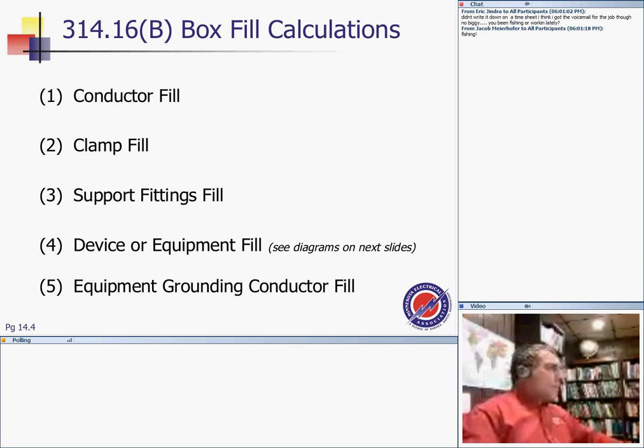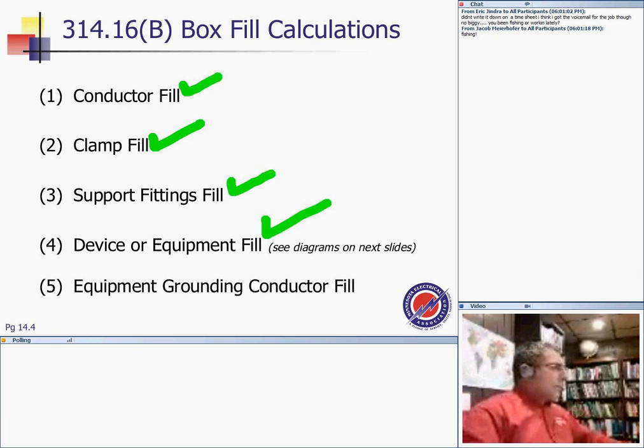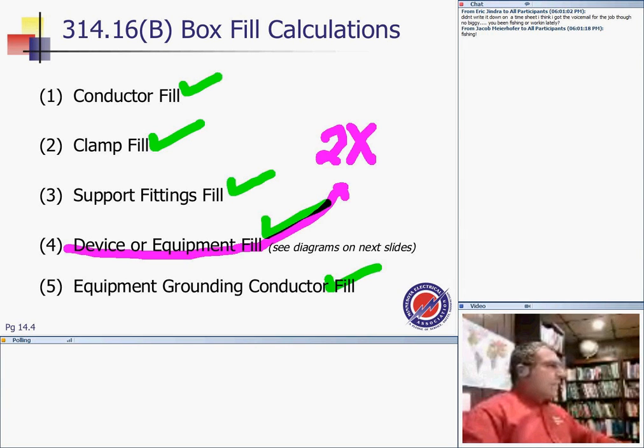So every conductor counts as 1. All clamps count as 1. Both fittings count as 1 each. Equipment grounding conductors all count as 1. Devices, guys, devices count as 2 based on the conductor landing on them. 2, based on the conductor landing on them.